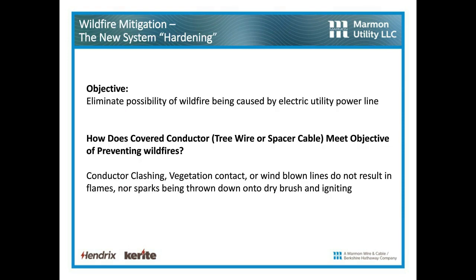So the objective: eliminate the possibility of wildfire being caused by an electric power line. And how does covered conductor spacer cable meet that objective of preventing wildfires? Essentially, conductor clashing, vegetation contact, or wind-blown lines do not result in flames nor sparks being thrown down onto the dry brush and igniting.